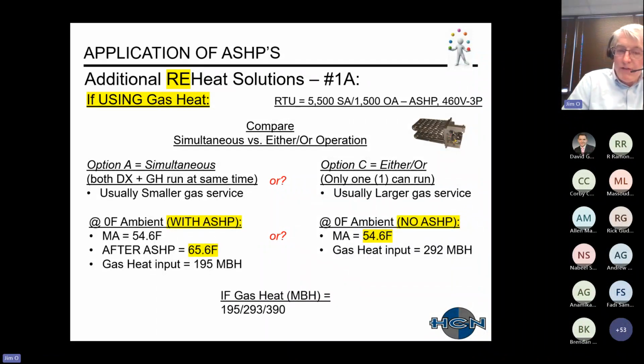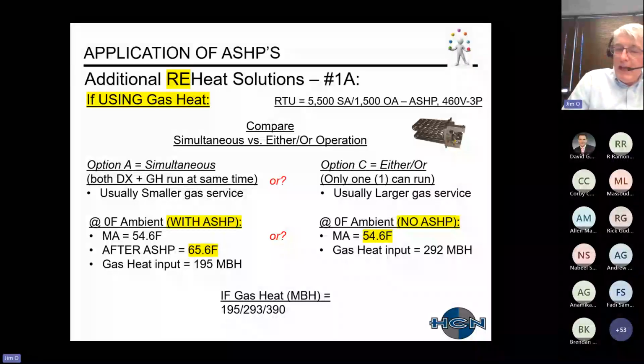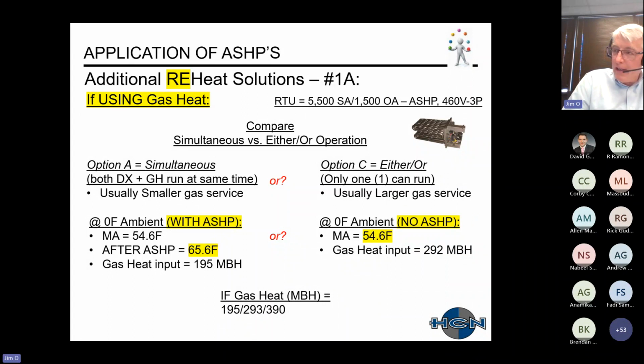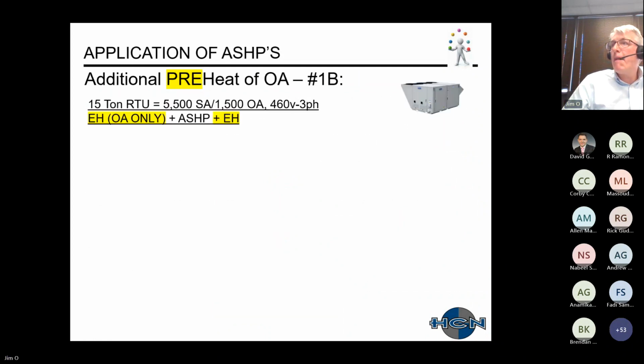And then I just want to point out too that traditionally gas heaters have much less options in terms of increments for heat. So this was a 15-ton unit that had 195, 293, or 390 input. So once again, you're kind of forced into one or the other. I would say that just to go from the 290 to 195 gas input is, I would say, chump change, but it's a small add to change that. Whereas electrical service, because you're often changing the MCA and a breaker or circuit breaker size on the unit, ends up sometimes more problematic.